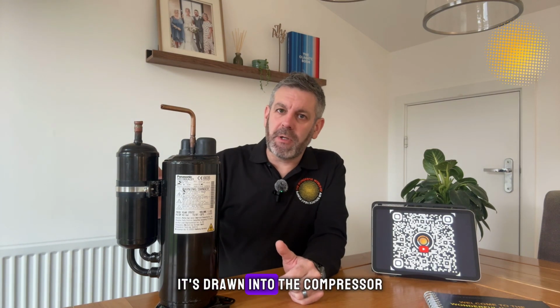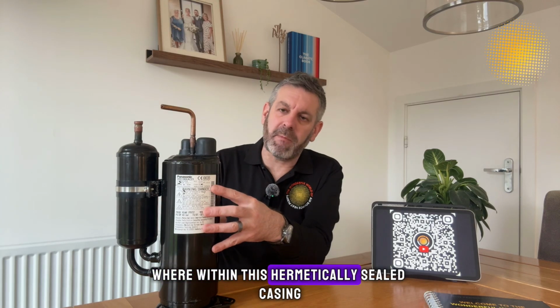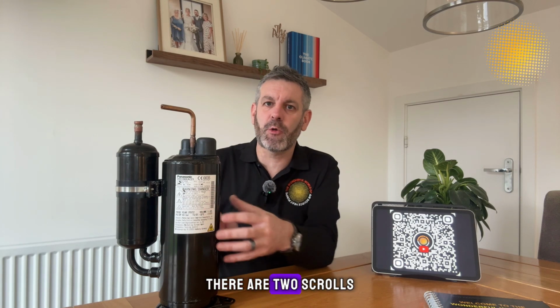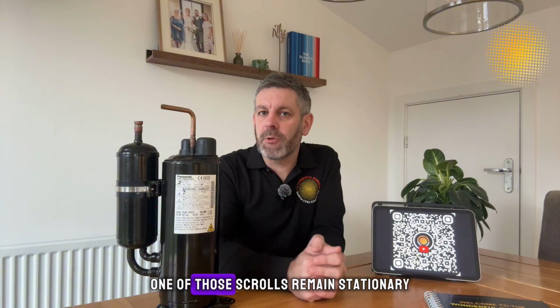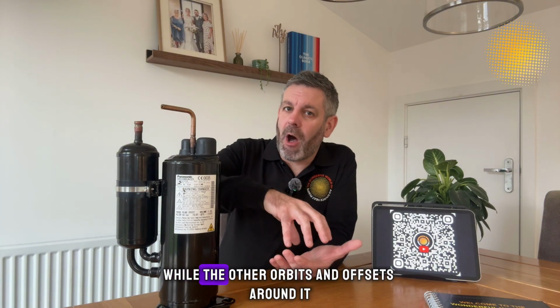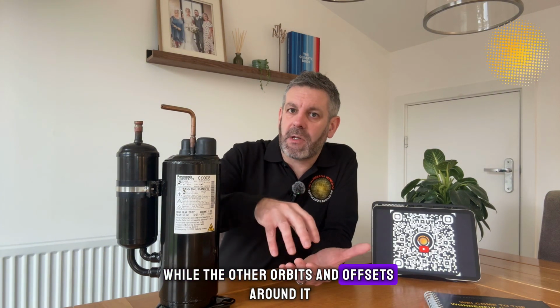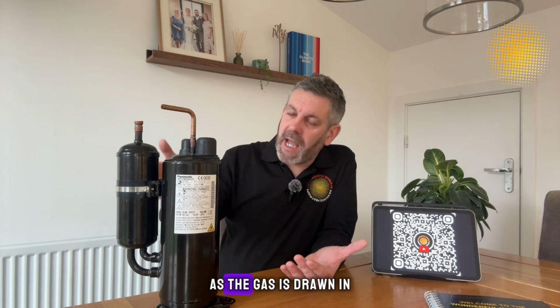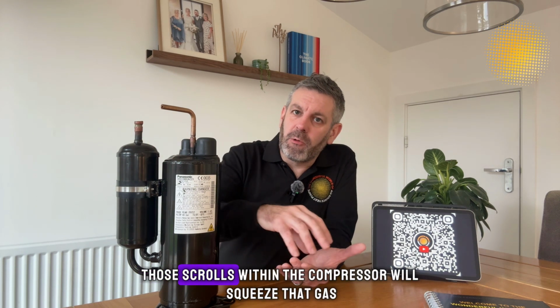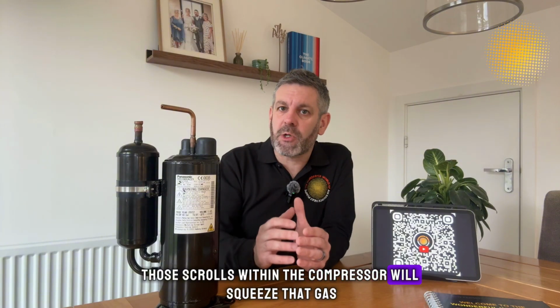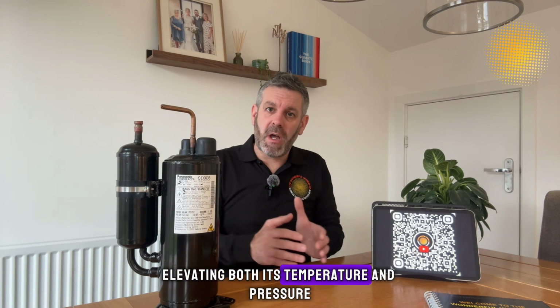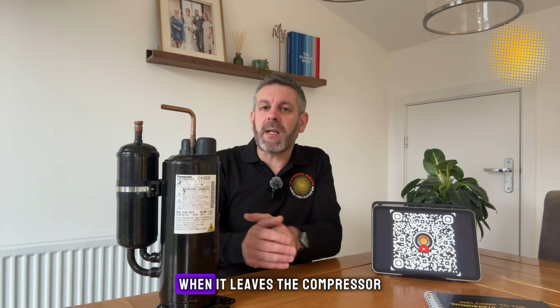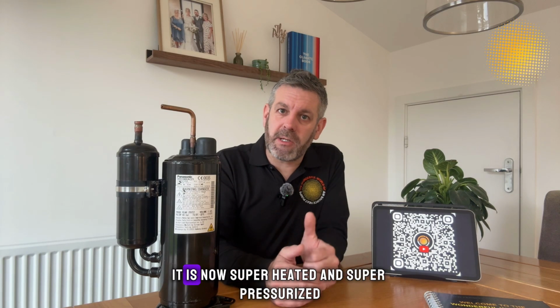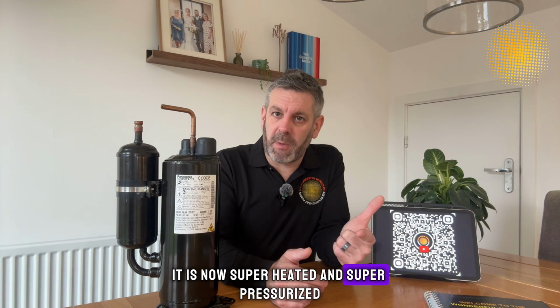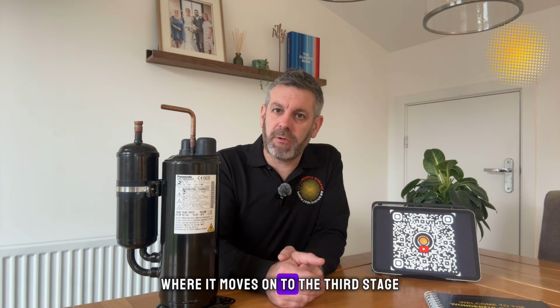It's drawn into the compressor, where within this hermetically sealed casing there are 2 scrolls. One of those scrolls remains stationary while the other orbits and offsets around it. As the gas is drawn in, those scrolls within the compressor will squeeze that gas, elevating both its temperature and pressure. When it leaves the compressor, it is now superheated and superpressurized, where it moves on to the third stage.